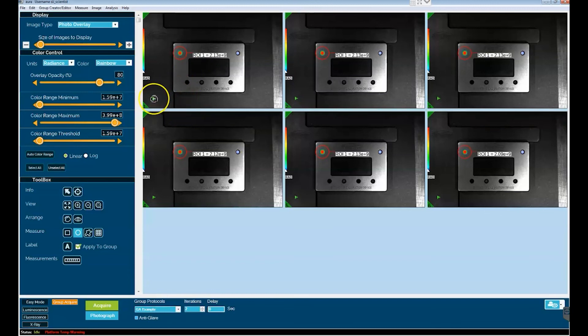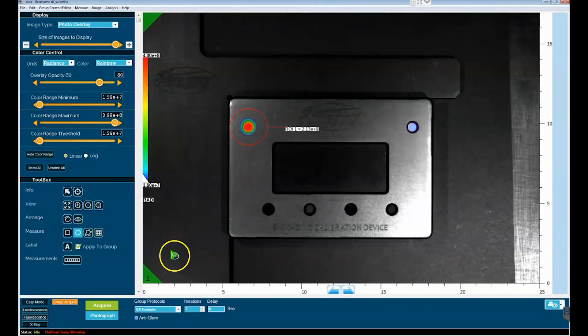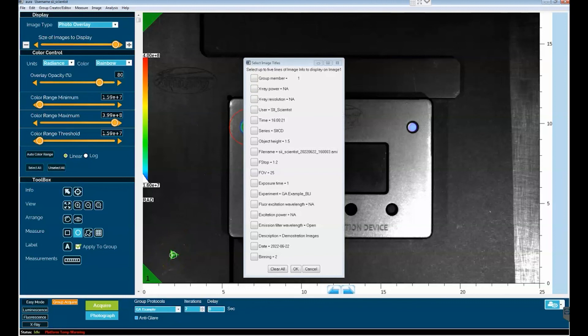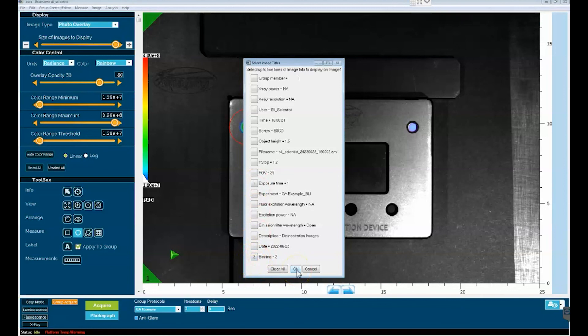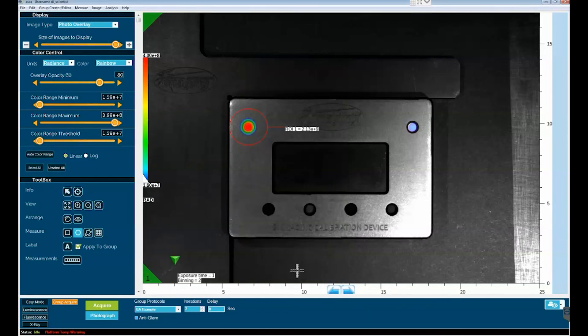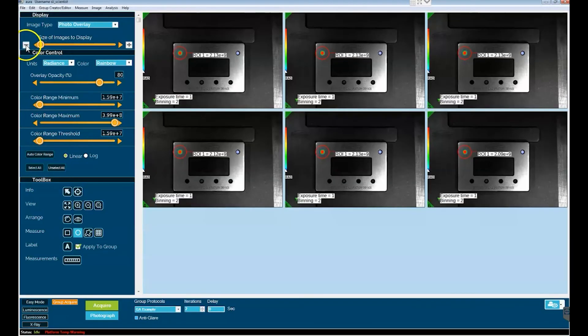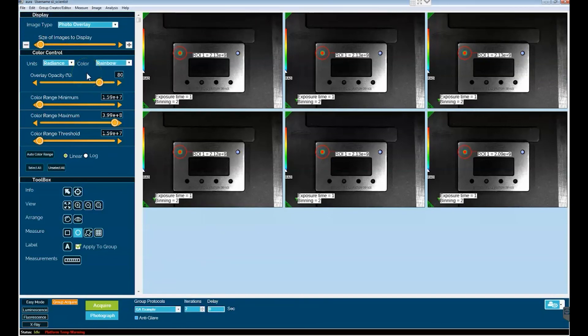Secondarily, let's say you want to do annotation. I want to double click on this to magnify this image. And now you can go to the green triangle, which will give you access to the metadata of the image. And you can, let's say, select exposure time and bin. If you happen to use variable settings here, this kind of annotation is very useful to keep track of which image had which acquisition settings. Click OK. Let's back out. And you can see that that annotation is applied to the entire group.